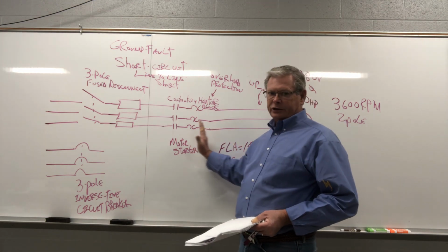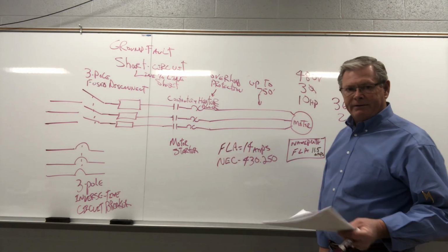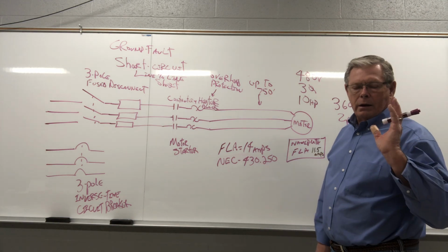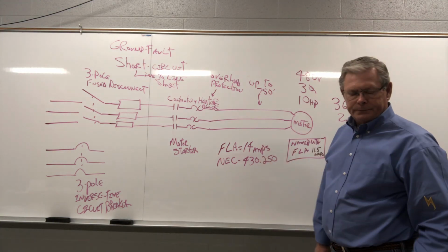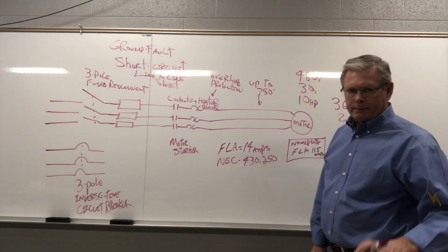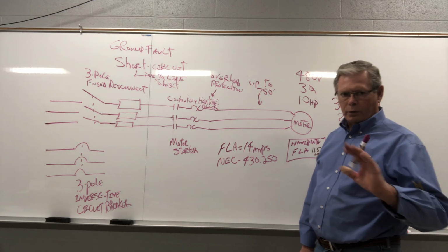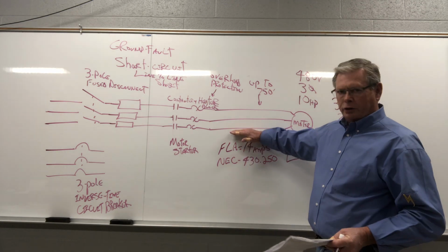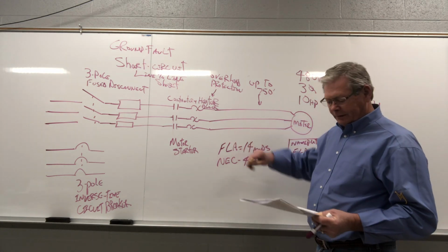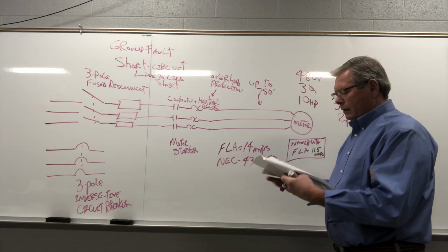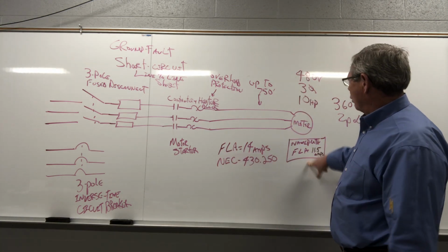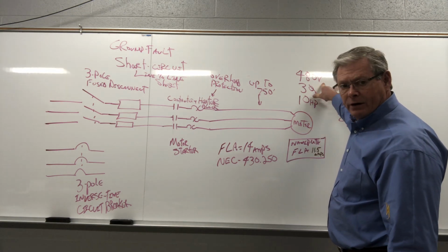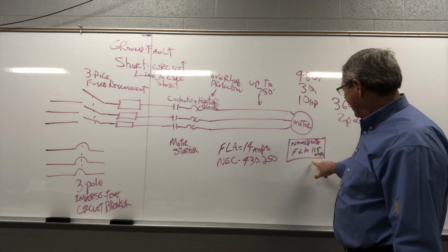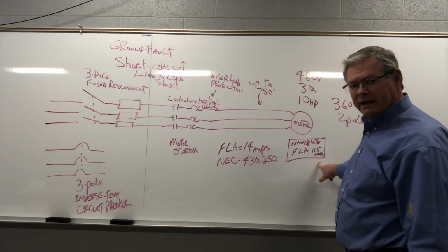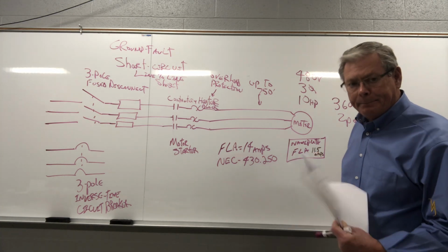Now, the calculations we're going to do are good for up to 750 feet distance between your starter and your motor. So that takes care of 99% of everything we do, okay? So don't worry about distance and voltage drop to your motor till you get past 750 feet. Now, let's get started. We have a 10 horsepower motor here at 480 volts, it's 3-phase, and it has a nameplate full load current of 11.5 amps, okay? I picked that.